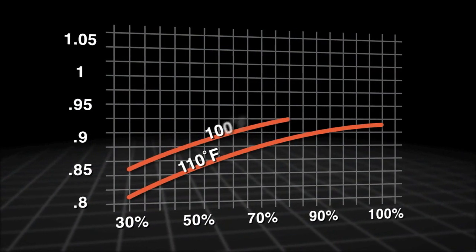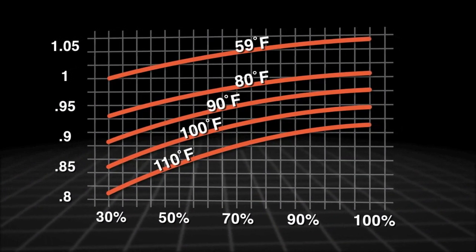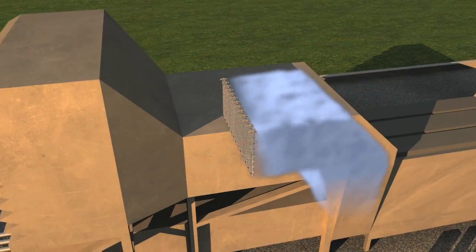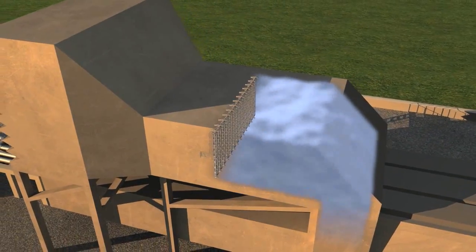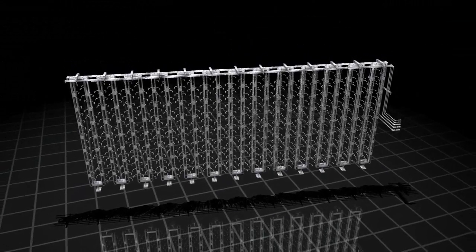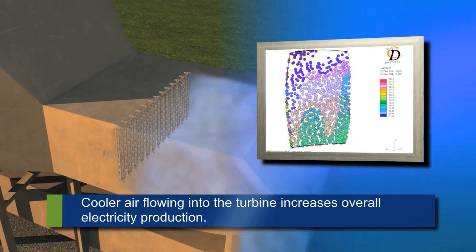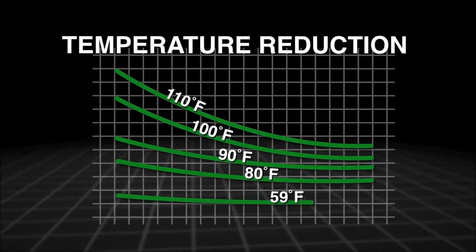Wood Group GTS's patented power augmentation technology reduces air temperature at the compressor intake by injecting water to generate a precise computer-controlled fog, resulting in increased turbine electricity production. Through careful design and detailed engineering analysis, the water injection locations, water flow rates, and injection control system ensure maximum water evaporation, creating a cooler temperature.